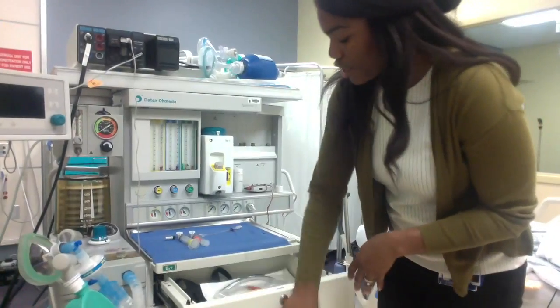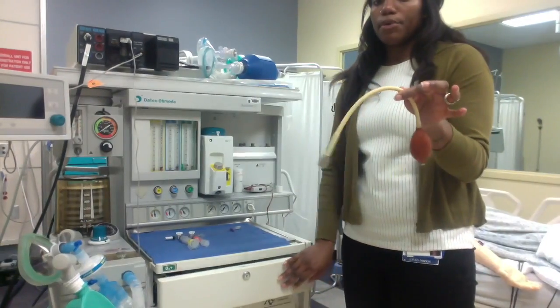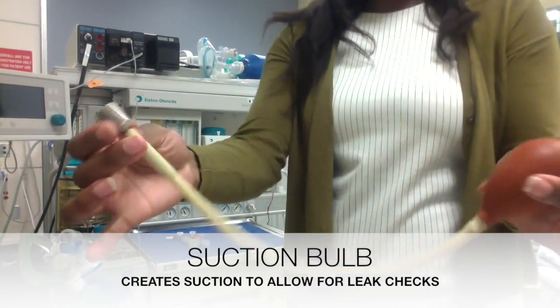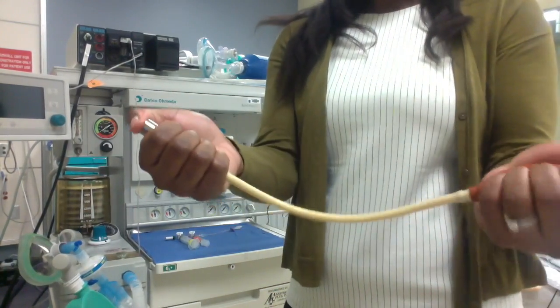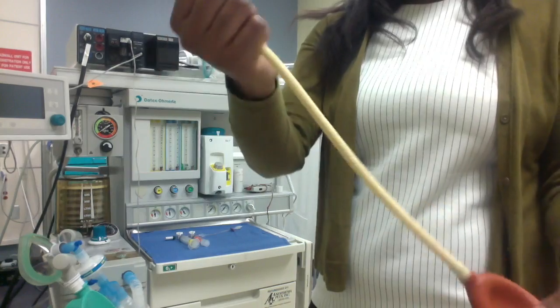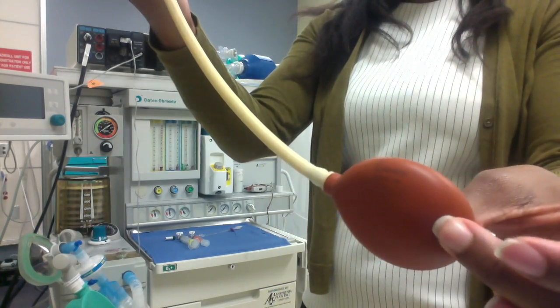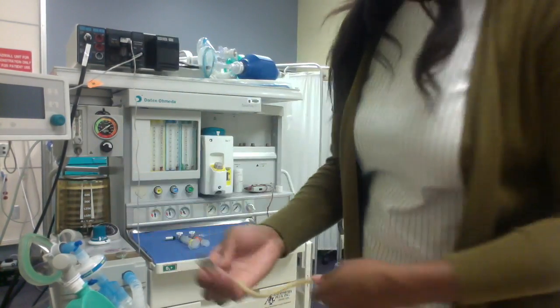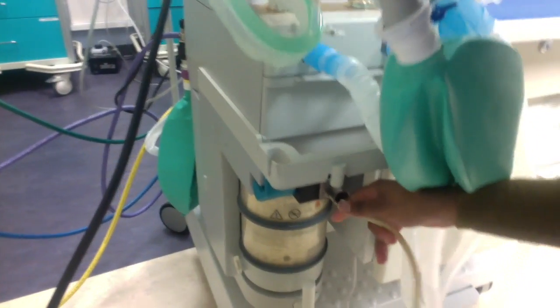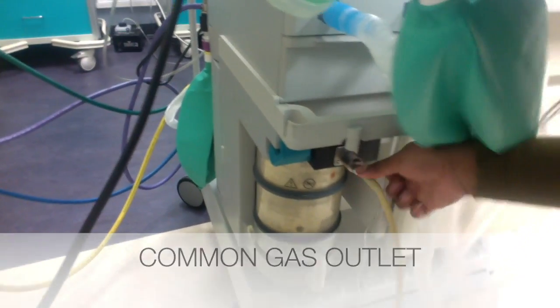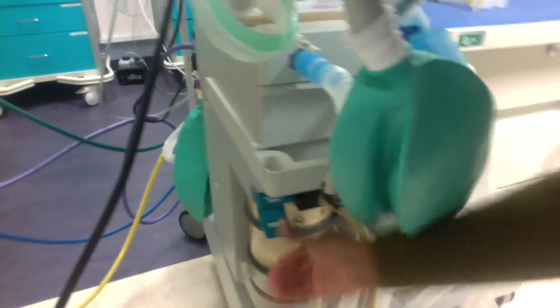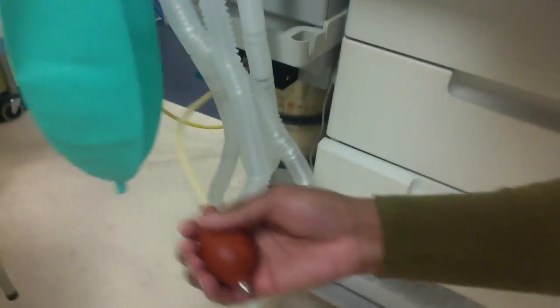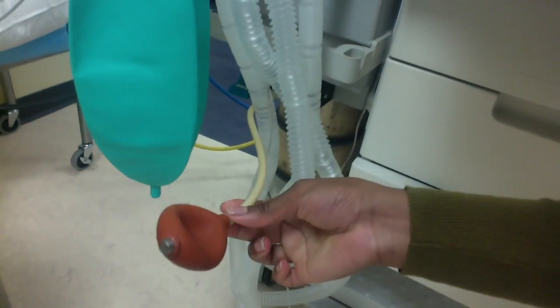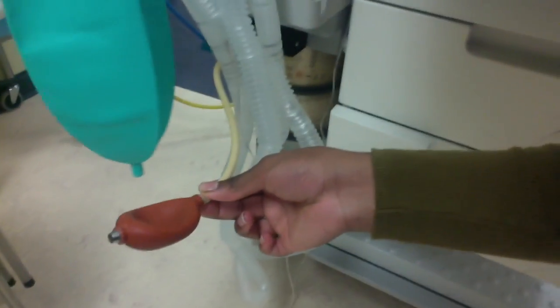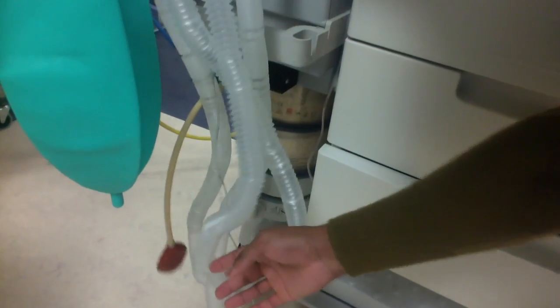I'll come and actually open up my drawer and find a bulb. This is just a bulb that you'll use to make sure that your circuit has no leaks in it. So first I'd make sure that this is working appropriately and that it's staying occluded for 10 seconds. And we'll say that it does. So then what I do is I connect it here. This is called your common gas outlet. And I'd flip this lever, and I'd squeeze this and occlude. The bulb should hold for 10 seconds. And so we'll say that that happened. We'll leave that hanging there.